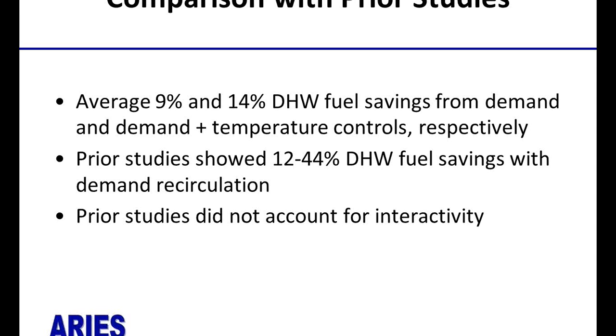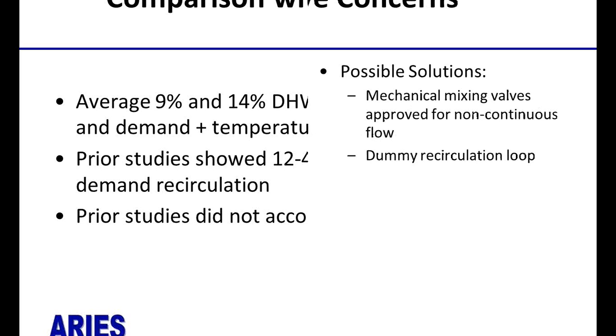So to bring this back to the prior studies that we found in our background literature, we've shown about an average of 9 to 14% fuel savings from the demand and demand with temperature modulation controls, respectively. Prior studies showing somewhere in that range, plus higher, with demand recirculation. But again, they didn't account for interactivity, and that might be responsible for some of the effects you're seeing here.